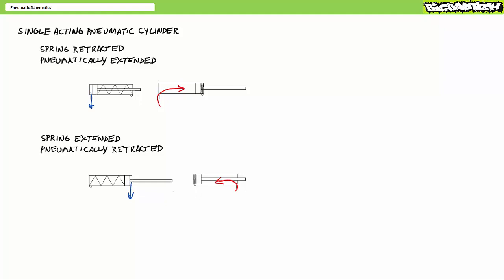The deactivated state of a spring retracted pneumatically extended cylinder is retracted, whereas the deactivated state of a spring extended pneumatically retracted cylinder is extended. When subject to pressurized flow, these cylinders change states. A spring retracted pneumatically extended cylinder extends, whereas a spring extended pneumatically retracted cylinder retracts. As I caution you in the pneumatic directional control valve lecture, sometimes the life and well-being of technicians and operators depends upon the proper interpretation of schematic symbols. Be sure you know what the deactivated and activated states of an actuator or valve imply to a larger pneumatic system.